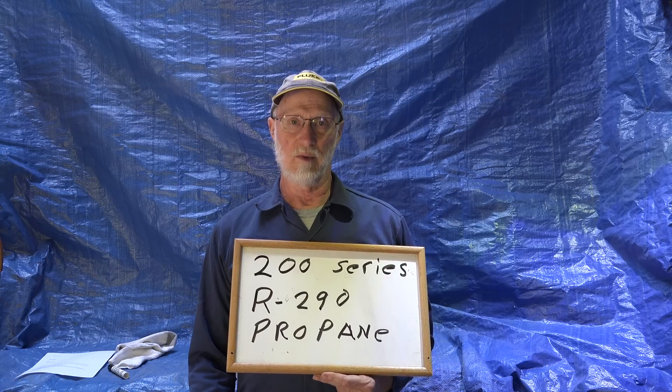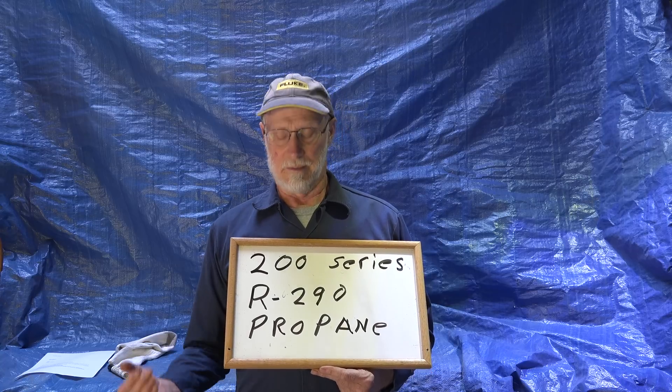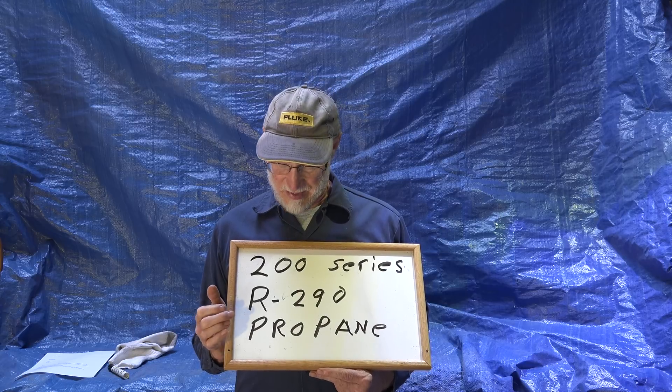There's a refrigerant called R22a that a company is selling as a replacement for R22 — it is actually propane, though they say it isn't. The biggest problem with propane in HVAC systems is if someone puts propane into an R22 system without marking it, a service tech could get in real trouble — blow himself up, blow the house up. So the 200 series is mostly propane. Next we'll go into the 400 series of blends.